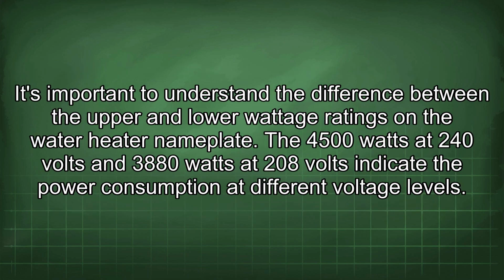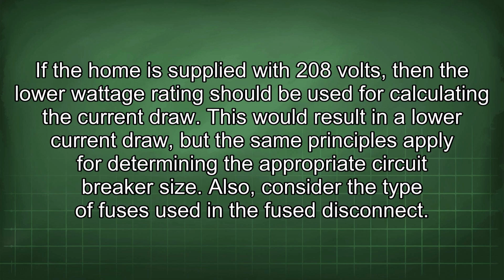It's important to understand the difference between the upper and lower wattage ratings on the water heater nameplate. The 4,500 watts at 240 volts and 3,880 watts at 208 volts indicate the power consumption at different voltage levels. If the home is supplied with 208 volts, then the lower wattage rating should be used for calculating the current draw. This would result in a lower current draw, but the same principles apply for determining the appropriate circuit breaker size.